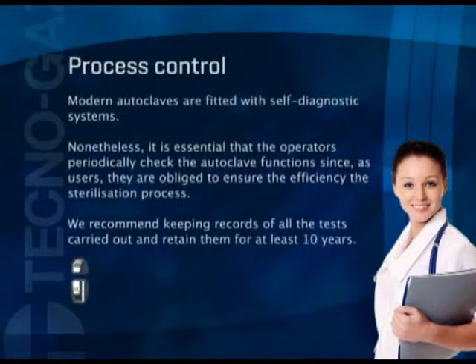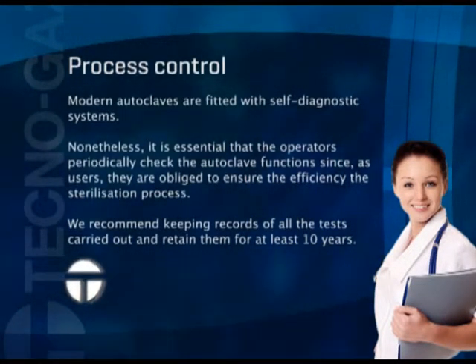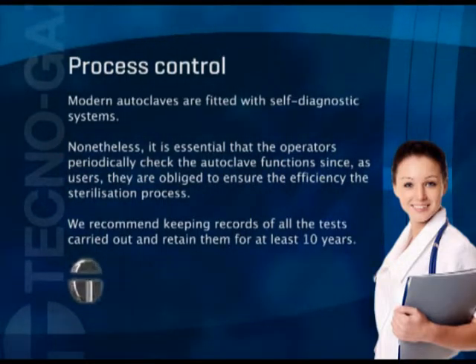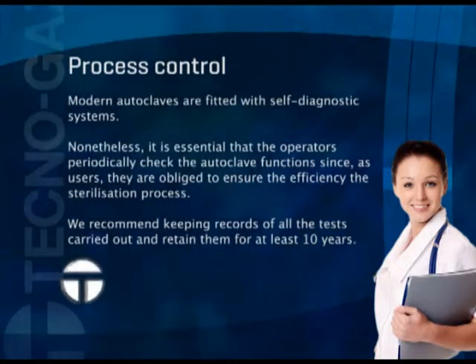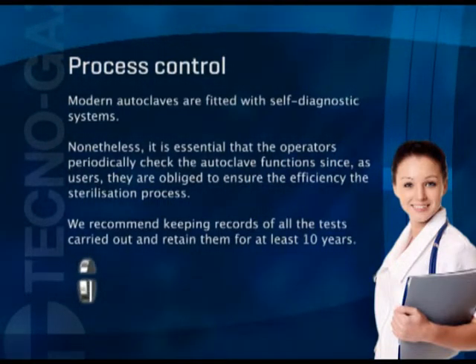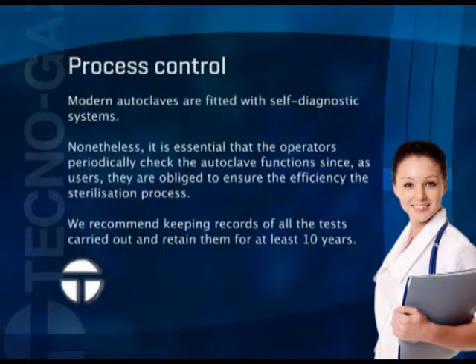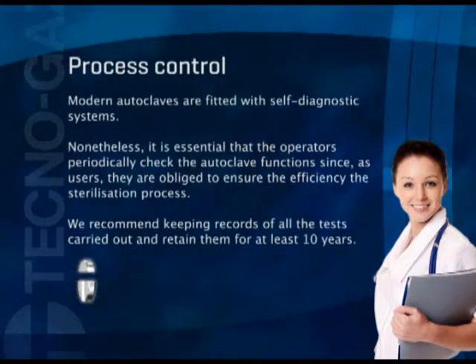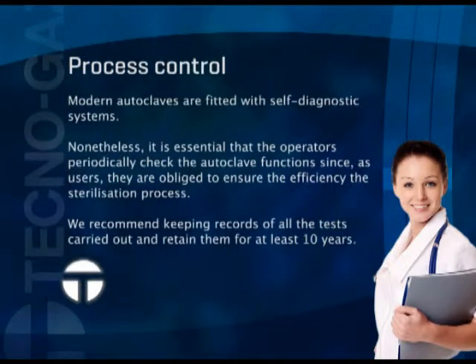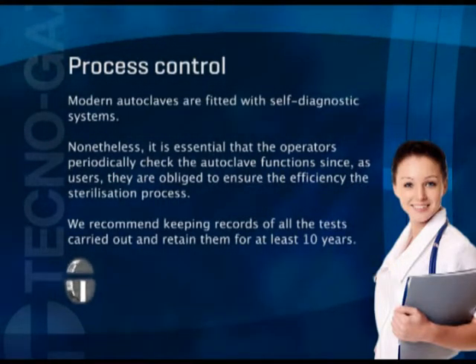Process control. Modern autoclaves are fitted with self-diagnostic systems. Nonetheless, it is essential that the operators periodically check the autoclave functions since, as users, they are obliged to ensure the efficiency of the sterilization process. We recommend keeping records of all the tests carried out and retain them for at least 10 years.